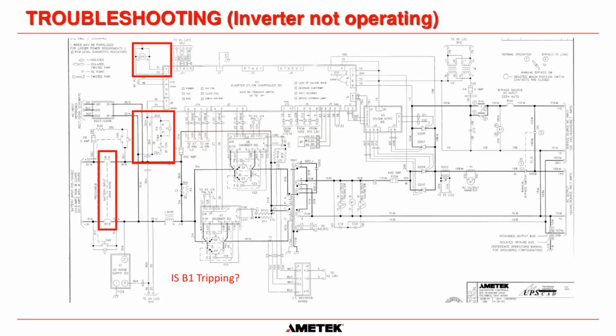So if the inverter is not operating and B1 is tripping, we need to make sure that K4 is working correctly. And there's two ways you can do it. If B1 is tripping and you think it shouldn't be, you can pull K4 out of its socket, which means this contact here will always be open, and then close the battery input breaker. And if it stays closed, then you know it's either something wrong with K4, or something wrong with the signal coming out of the board that energizes K4. And then you'd have to do some troubleshooting. If the voltage is greater than 105 volts and K4 is still energizing, then there could be a software setting or something wrong with the control board there.